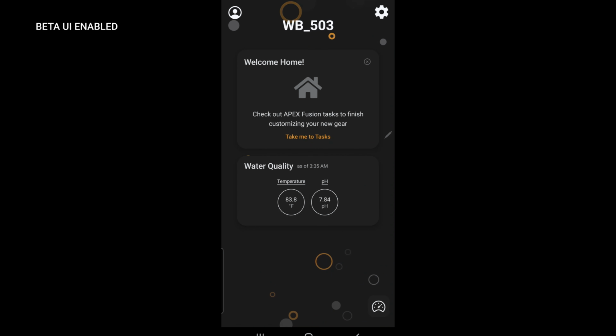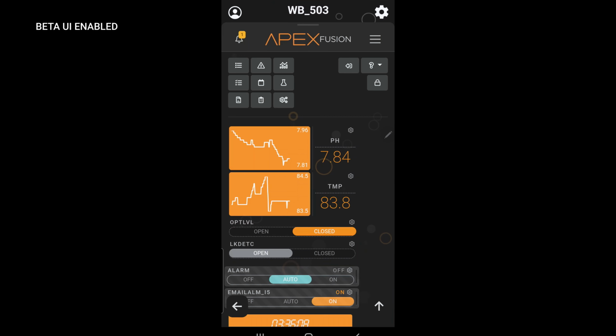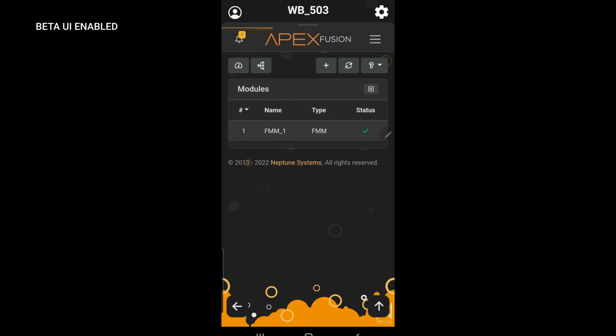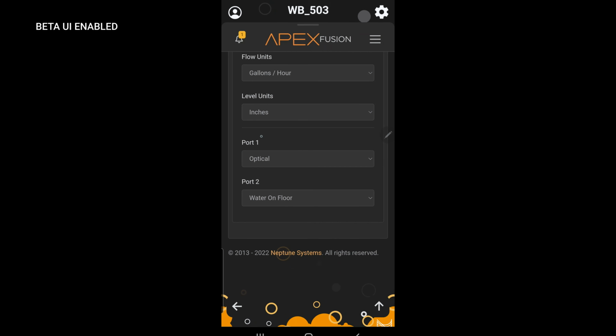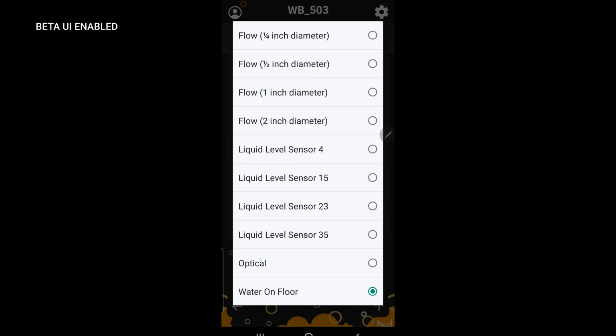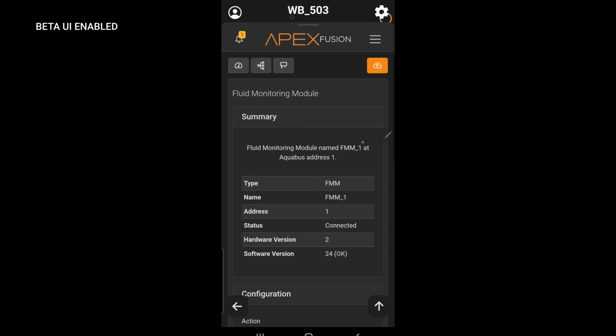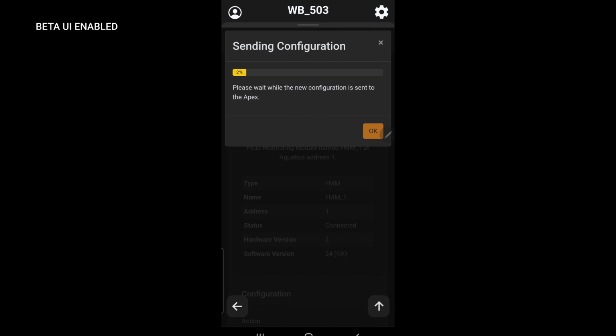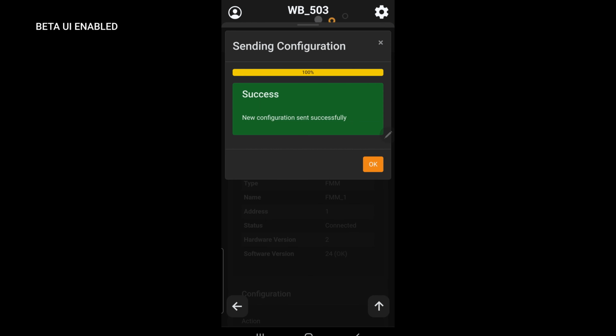To configure the optical sensor, just first plug it into port 1 or 2. Next, go to dashboard, then select module icon. Select the module where you connected it. If you connected it in port 1, make sure to select the optical from the drop-down list. I connected my leak detector in port 2, so in my drop-down, I selected water on floor. So once you're done setting port 1 and port 2, scroll up and click the orange cloud icon to upload your configuration to your Apex Junior device.